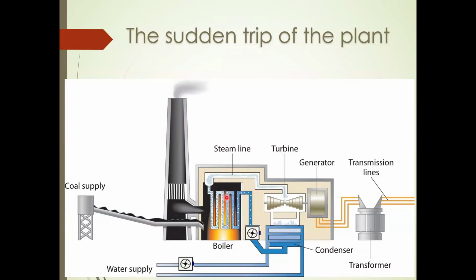It's not shown here. And of course, steam is being directed to the turbine, and the turbine rotates. On the same shaft, you have the generator here. And then the exhaust of the turbine goes directly into the condenser. Of course, cooling water is there. It cools down. And the terminals of the generator are connected to the transformer, and via the transformer it connects to the grid, the transmission line.